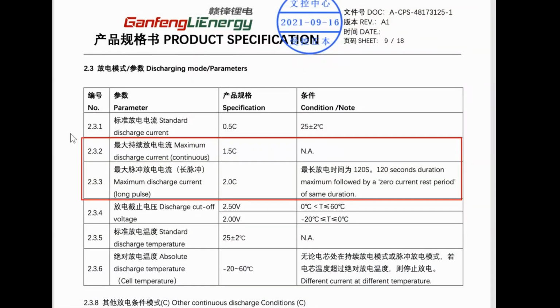So I inquired with DFUN about the high discharge rate, and they sent me this updated spec sheet from Ganfeng, and it does say maximum discharge current continuous 1.5 C, which would be around 150 amps. So they tell me that they set their BMS at 160 to disengage after 10 seconds of time. So that's why I was able to see above 100 amps when I was doing my discharge test.